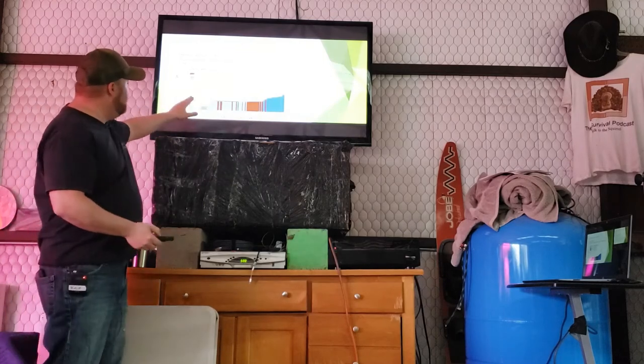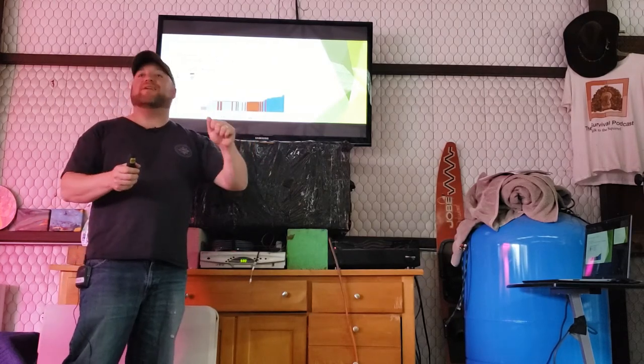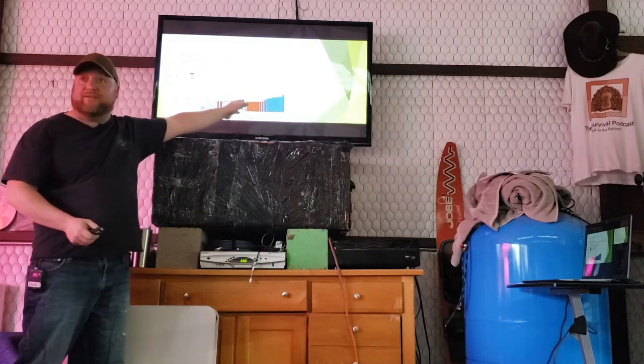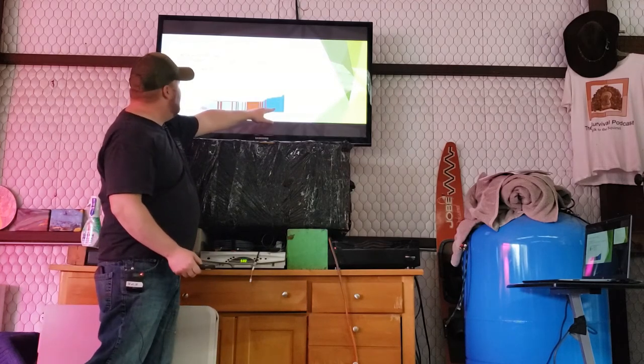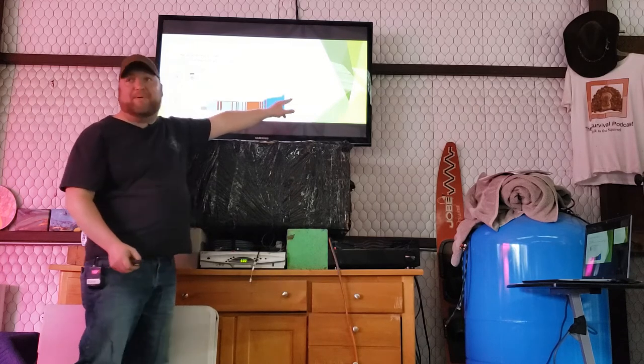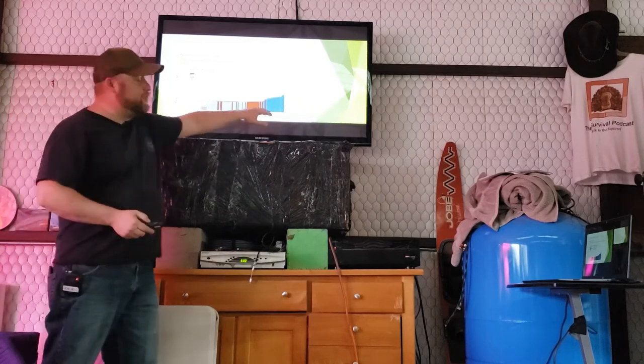So they're saying, okay, here's the stack. Everyone has bid on what the consumer, or the distribution company at least, is gonna buy the electricity at. We buy the cheapest first, and then we ramp up, so the very last megawatt that we generate is the most expensive. And as you can see, over here, the dark blue would be peaking plants, right? So these are the older style where you're just running it like a generator, basically. Those are the most expensive.